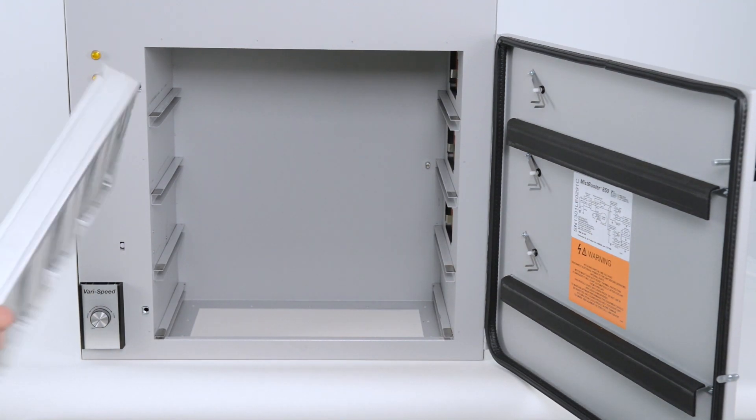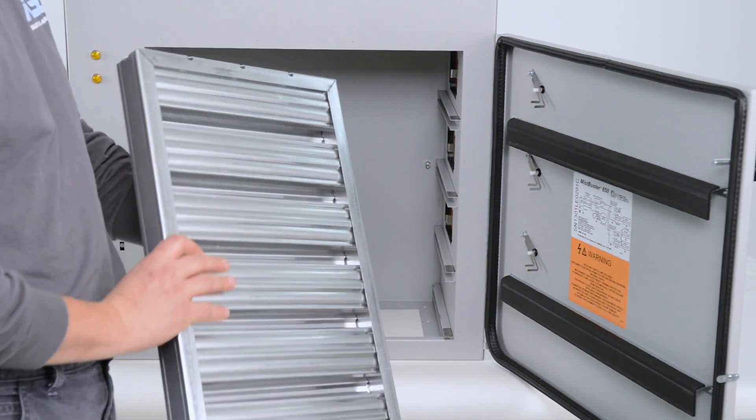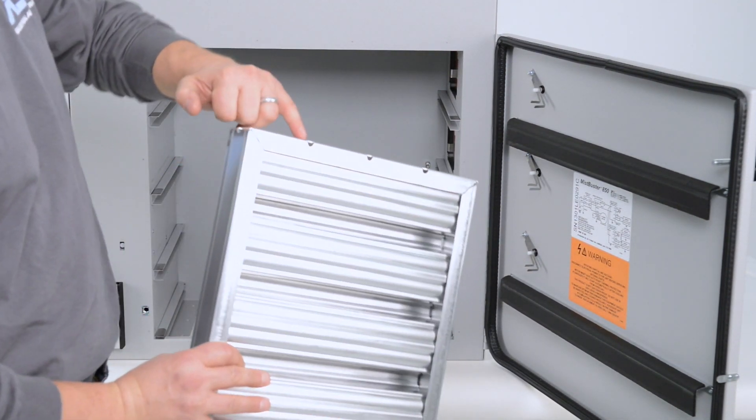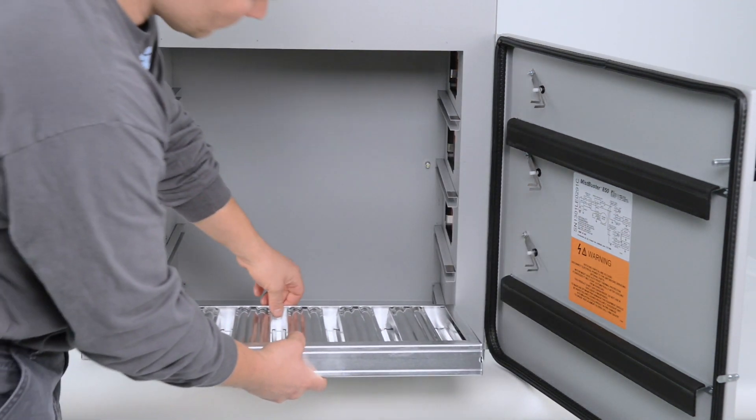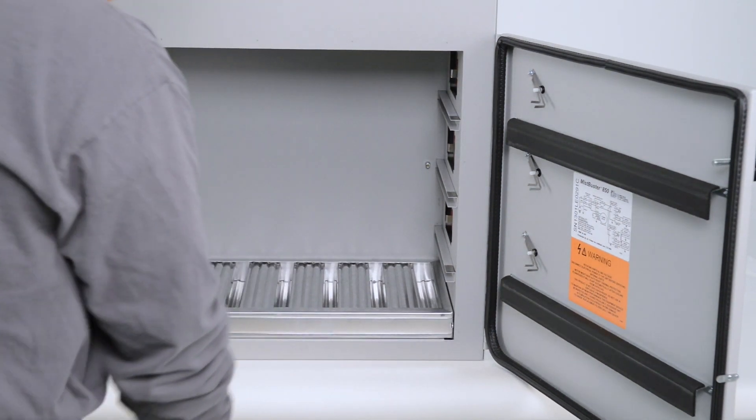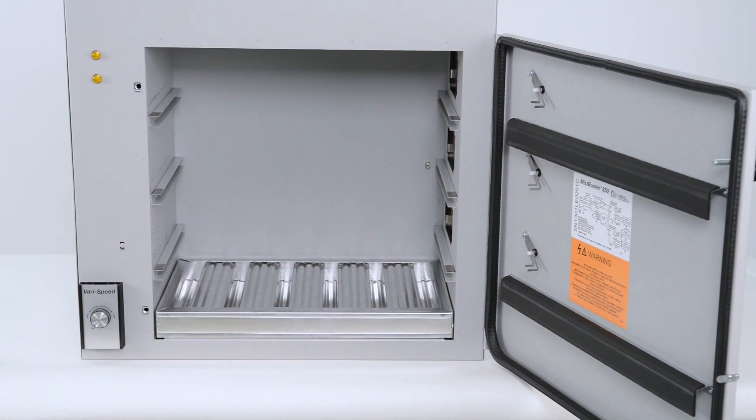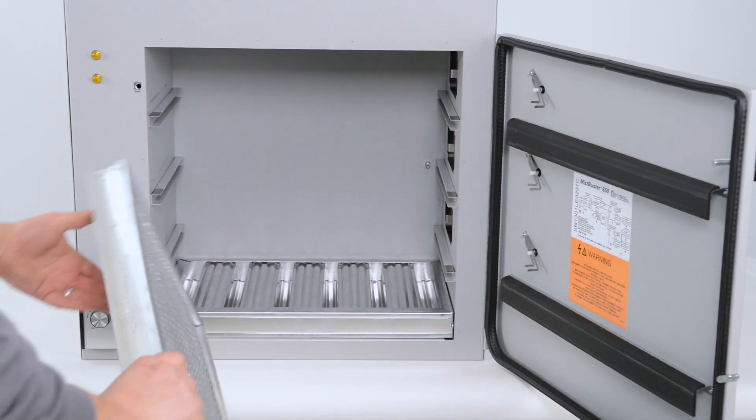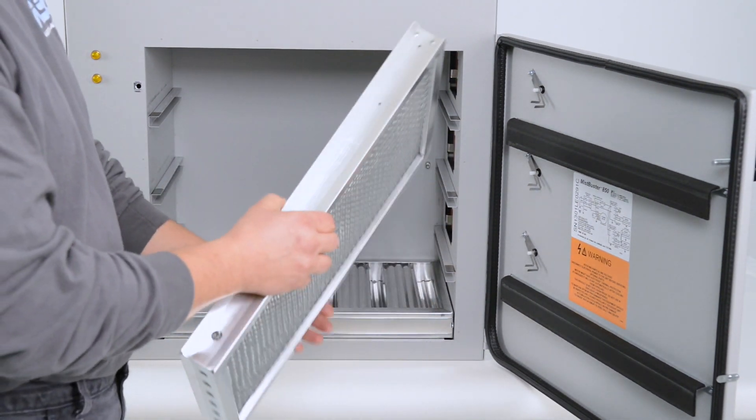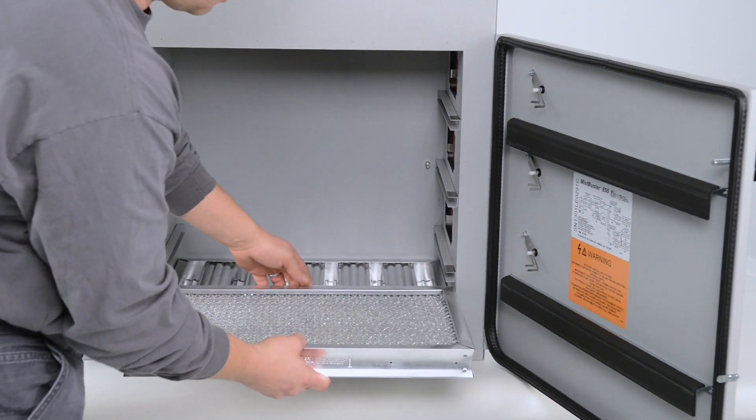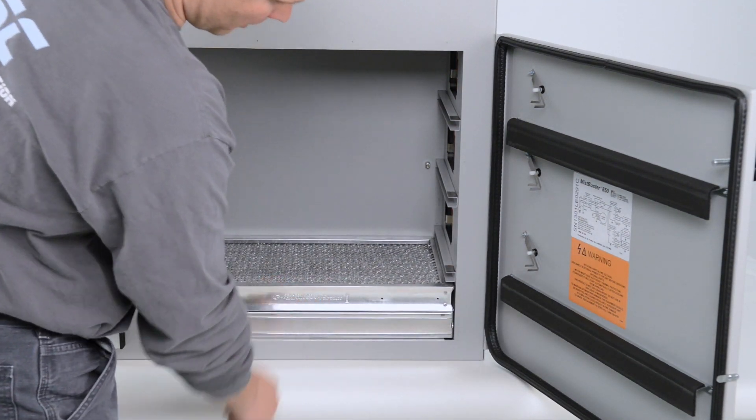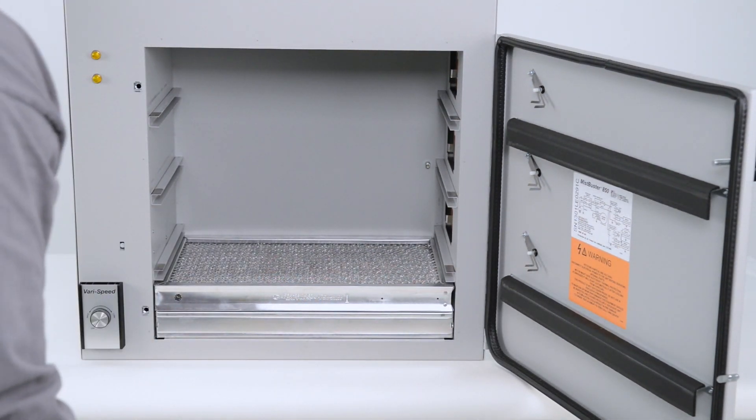When reinserting the new cells, you need to put the grease trap impinger section first with the drains pointing down. The second stage filter has an arrow pointing up, and you want to place that directly above the first impinger.